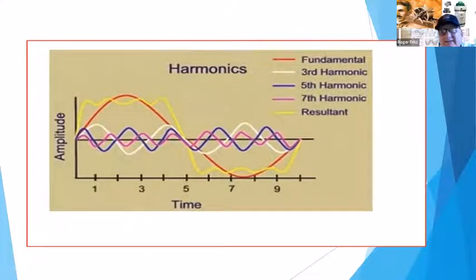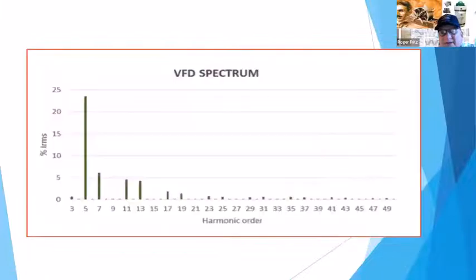We're actually seeing low voltage color feeders, the ones that fed the color of the molding product, changing color, because they were 12 and 24 volt DC circuits that were ungrounded. These noise levels would show up in the circuits, and what would happen is it would change the fundamentals. A lot of electronics have got a lot better and have eliminated some of these things, but there are some weird phenomena you have to be careful of.